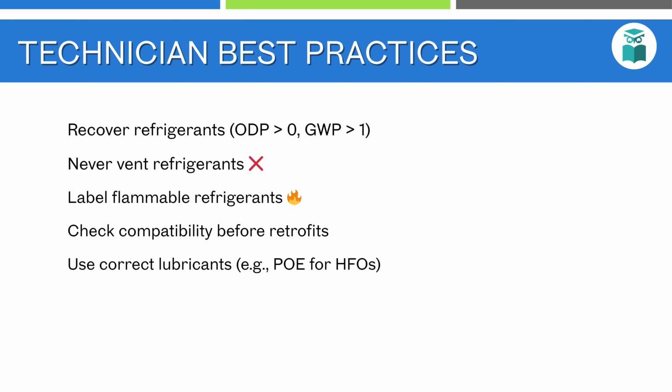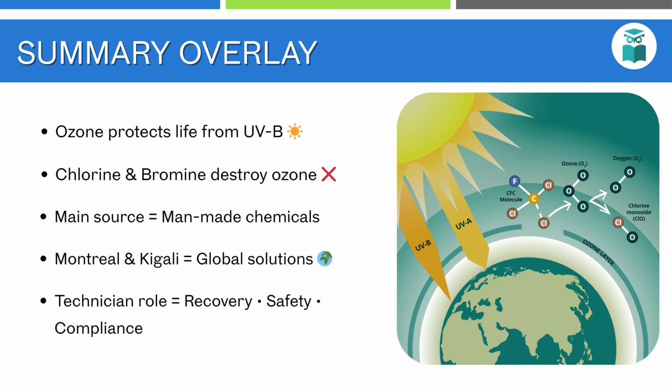For example, HFOs require synthetic POE oils. And remember, hydrocarbon systems like R600A must use extremely small charge sizes and must be clearly labeled due to flammability risks. Okay, to sum it up, the ozone layer protects us from UV radiation.